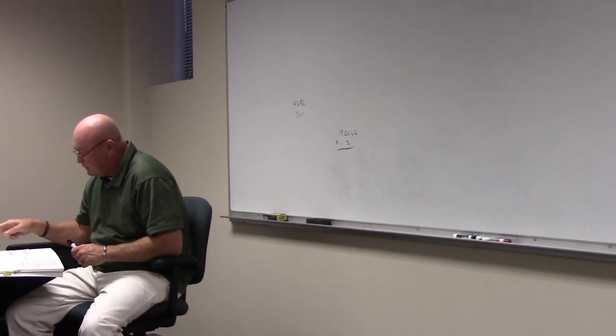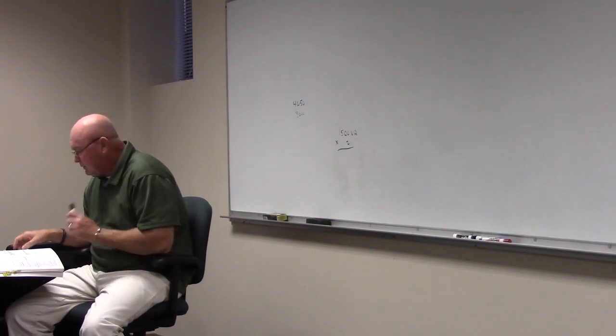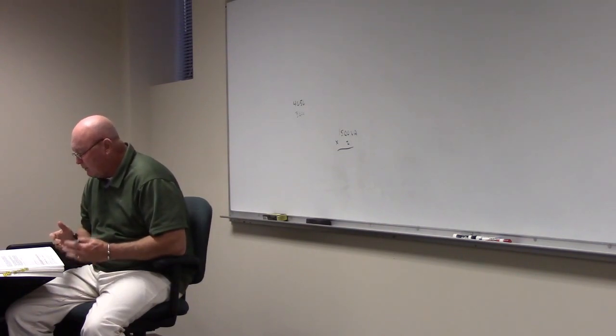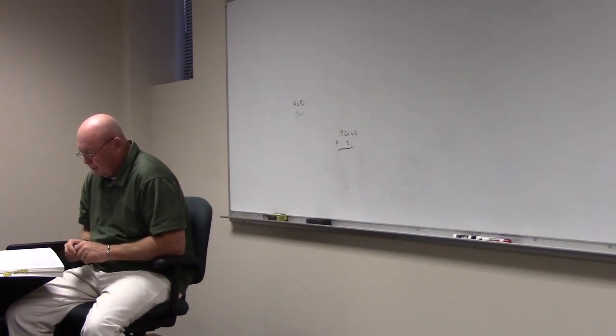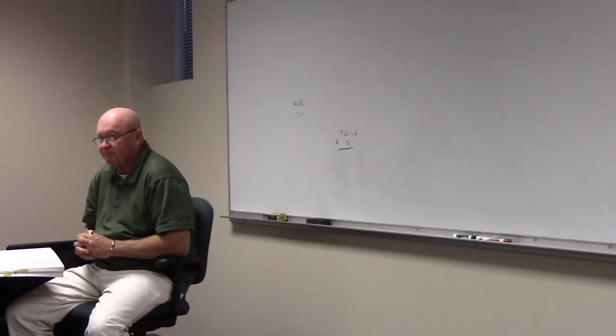Other small appliances also says 220.52, so when we're right there, 220.52 states a small appliance circuit to be rated at 1,500. That's where we get to 1,500. Let's turn there to check so we just didn't get that out of the clear blue air. Because really, I'm sure somebody wanted to ask, why 1,500? Because 220.52(A) says small appliance circuit load. Each dwelling load shall be calculated at 1,500 volt amps for each 2-wire small appliance. Y'all see that there? That's why we did it. So that's why we got 2.